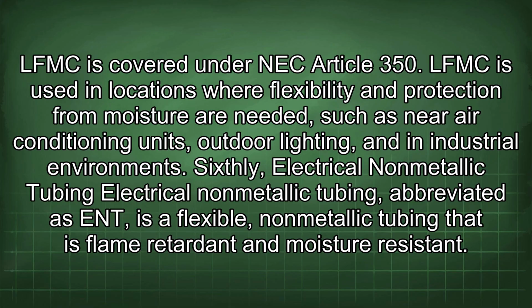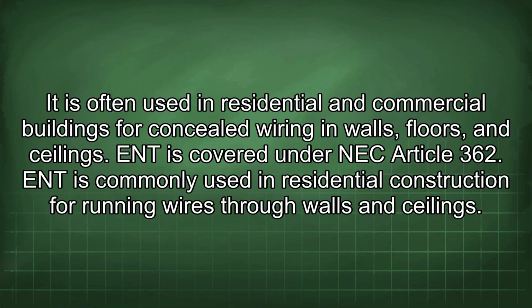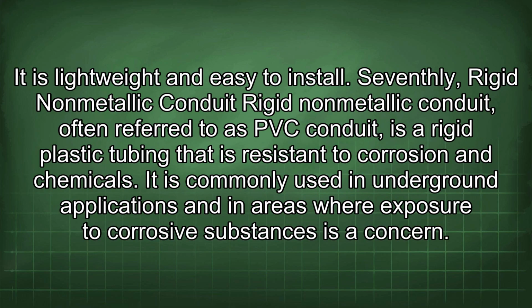Sixthly, electrical non-metallic tubing. Electrical non-metallic tubing, abbreviated as ENT, is a flexible, non-metallic tubing that is flame retardant and moisture resistant. It is often used in residential and commercial buildings for concealed wiring in walls, floors, and ceilings. ENT is covered under NEC Article 362. ENT is commonly used in residential construction for running wires through walls and ceilings. It is lightweight and easy to install.